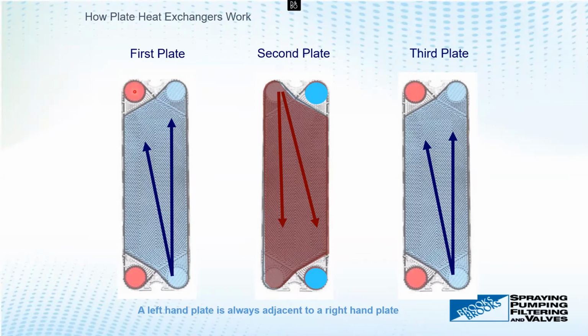We do that for as many plates as your plate pack is intended. All these grooves or corrugations are designed to release heat and give you the most turbulence and pressure drop needed for your system, minimizing the plates while maximizing the efficiency of your heat exchanger.